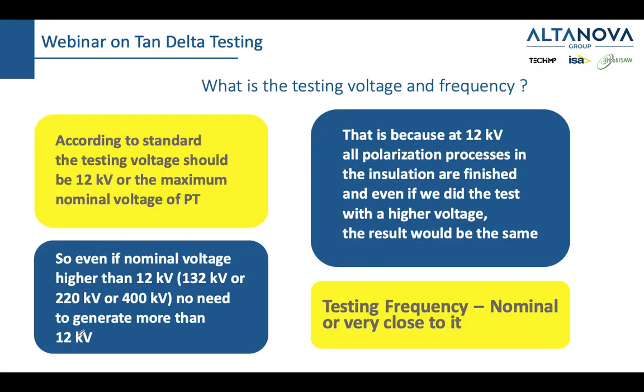Now, let us discuss the nominal value at which you should measure tan delta. What is the actual value of voltage which should be applied when measuring tan delta? First of all, it is not necessary and in many cases not possible to generate more than 12 kilovolts. Why is this so? It's so because at 12 kilovolts, all the polarization processes inside of your insulation are done. Even if you would generate 200 kilovolts instead of 12 kilovolts, you wouldn't get a different result. So 12 is, or very often people use 10 kilovolts, but 12 is, let's say, the prescribed value. And of course, you need to keep in mind the voltage level of your transformer. If you have 10 to 0.4 and you're generating on the low voltage side, you cannot generate more than the nominal voltage. So please be aware of that.